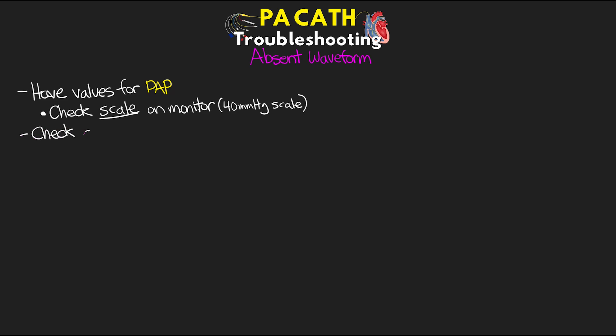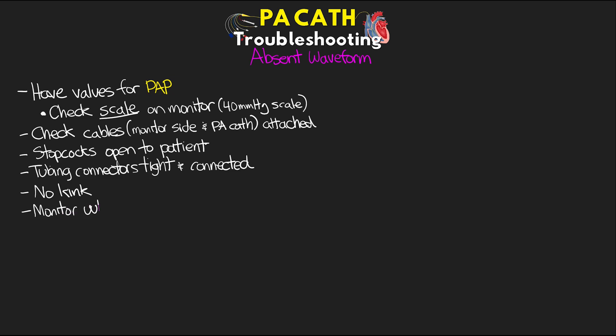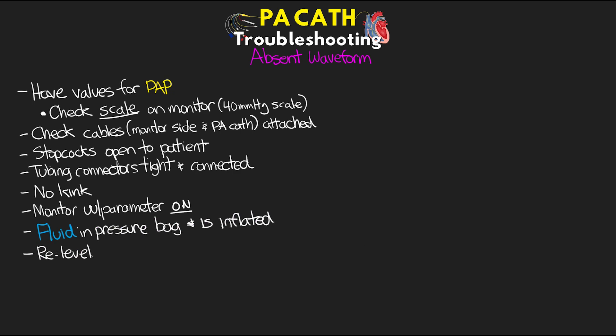From there, check and make sure that all the cables — both the monitor end and the PA catheter patient end — are securely attached. Check all your stopcocks to ensure that you have an open path from the patient to the transducer. Make sure all pressure tubing connections are tight and connected to the PA catheter, check for any kinks in the system, and ensure that the monitor actually has the PA catheter parameter turned on. Also make sure that you have enough fluid in your pressure bag and that it is appropriately inflated, then re-level and zero.